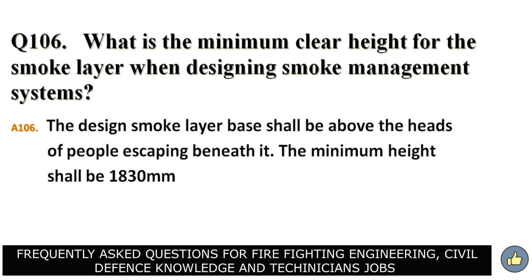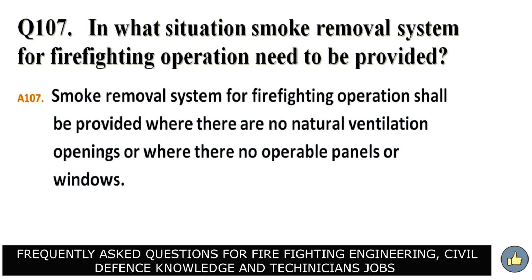What is the minimum clear height for the smoke layer when designing smoke management systems? Answer. The design smoke layer base shall be above the heads of people escaping beneath it. The minimum height shall be 1830 millimeters. In what situation does a smoke removal system for firefighting operation need to be provided? Answer. Smoke removal system for firefighting operation shall be provided where there are no natural ventilation openings or where there are no operable panels or windows.